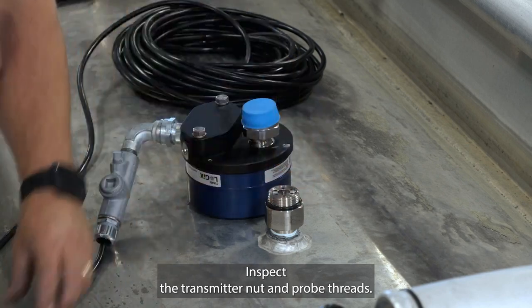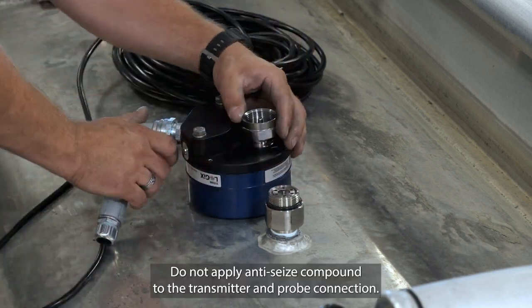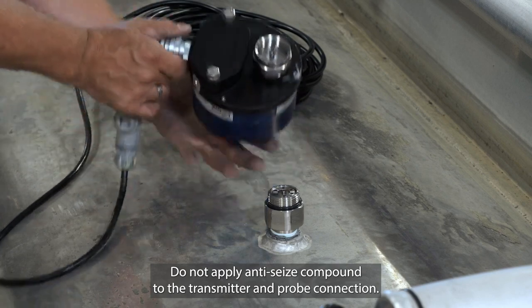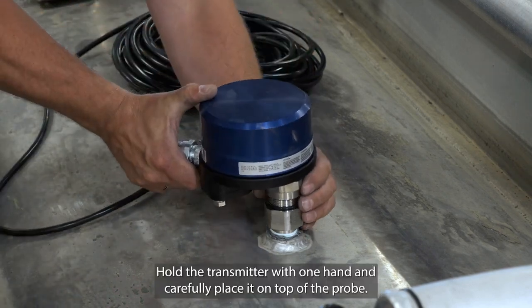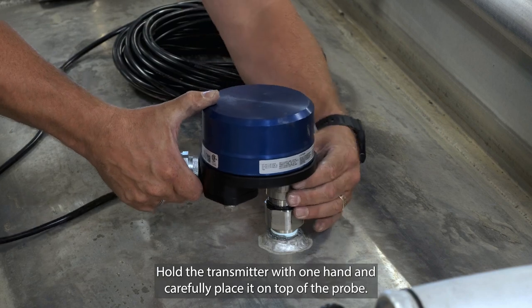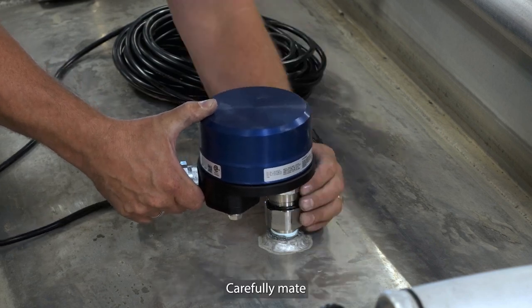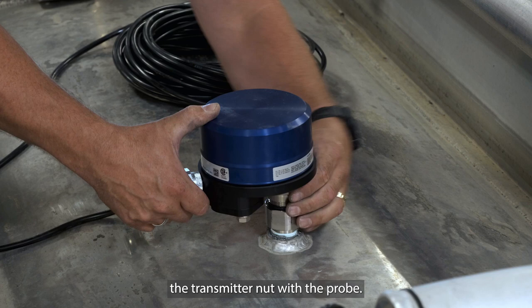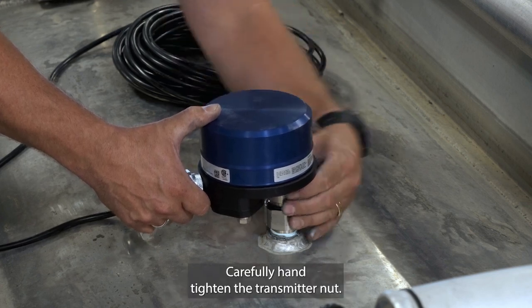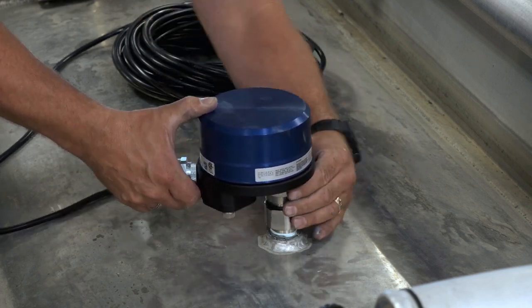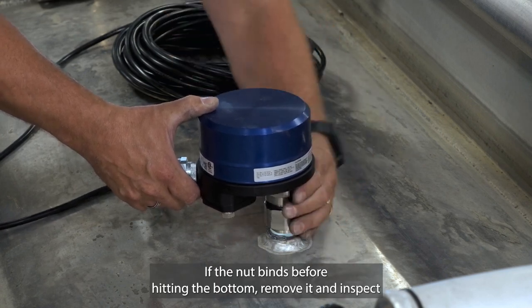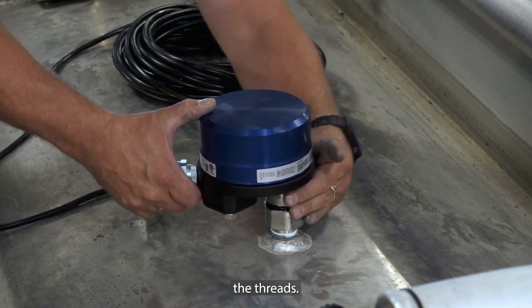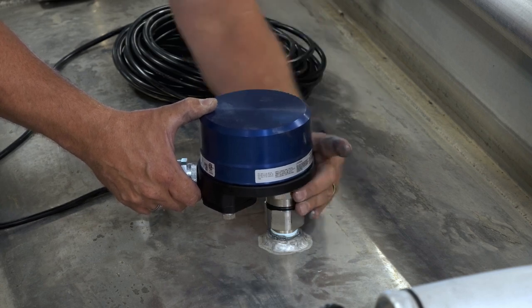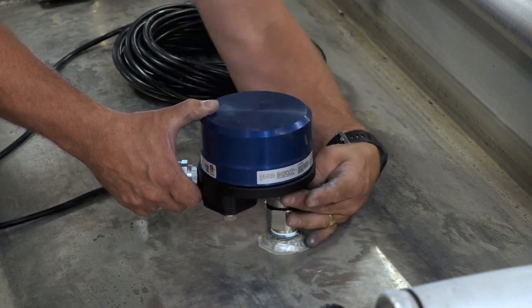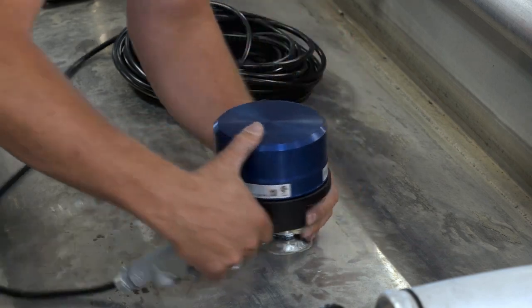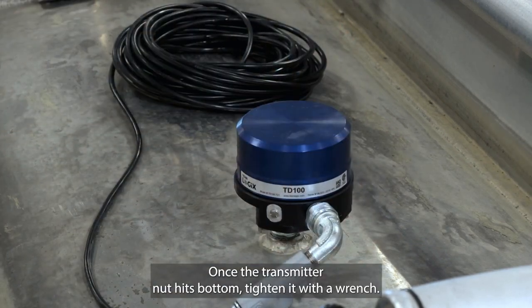Inspect the transmitter nut and probe threads. Do not apply anti-seize compound to the transmitter and probe connection. Hold the transmitter with one hand and carefully place it on top of the probe. Carefully mate the transmitter nut with the probe. Carefully hand tighten the transmitter nut. If the nut binds before hitting the bottom, remove it and inspect the threads. Once the transmitter nut hits bottom, tighten it with a wrench.